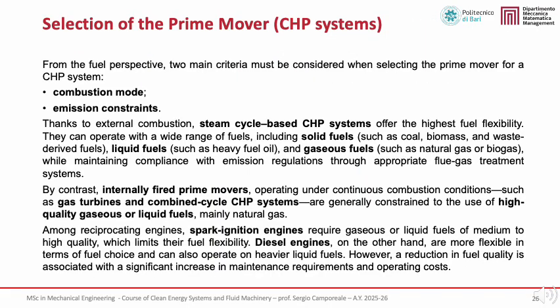Fuel availability and emission constraints are fundamental factors in the selection of the prime mover in CHP systems. Two main aspects must be considered: the combustion mode and compliance with emission limits. Steam cycle-based CHP systems operate with external combustion and therefore offer the highest fuel flexibility. They can use a wide range of fuels, including solid fuels such as biomass and waste-derived fuels, liquid fuels such as heavy fuel oil, and gaseous fuels such as natural gas or biogas. In these systems, emission limits are mainly addressed through flue gas treatment technologies.